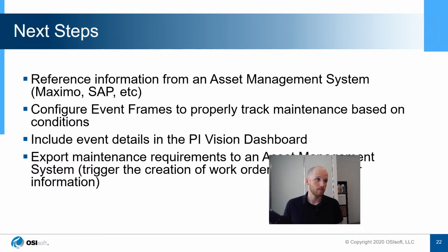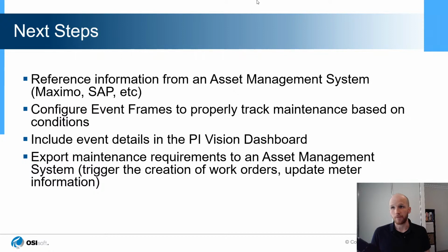So say, for example, you had the expected efficiencies of all these pumps, depending on how much power was being put into them, depending on different specs in an asset management system. Then you could import data from that asset management system into Asset Framework and use that as the threshold for the alarm. You could create event frames. So when the alarm is surpassed, when the pumps have gone underneath this expected efficiency, send out emails or even trigger work orders on a system like SAP or Maximo.